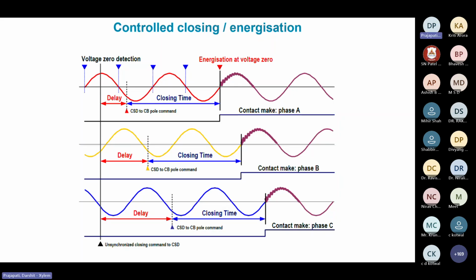So if it is not targeted at the zero, the oscillations which you can see might be significant, and can lead to early erosion of the contact. In other terms, it reduces the life of the contact, the available life of the contact in the field. This is for the closing or the energization.